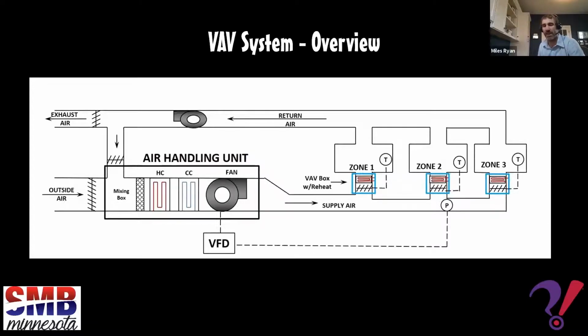And if we're controlling on that and the space continues to overcool, well, then we'll start to raise the temperature of the air being sent into that space by modulating a control valve, which is serving the reheat coil in that respective VAV box. So the cool thing about variable air volume systems is with one air system, you can have some zones calling for heating and some zones calling for cooling and be able to satisfy all of those thermal zones. Now, as those dampers in all the respective VAV boxes are opening and closing, the static pressure in the supply air duct is going to be changing a bit.